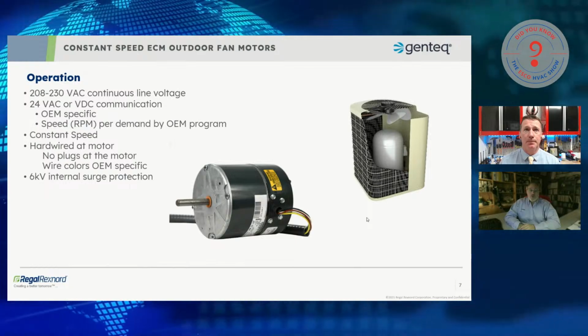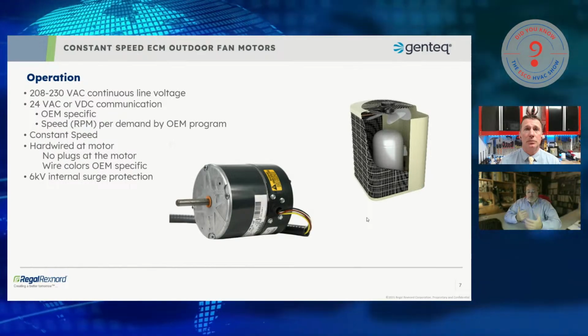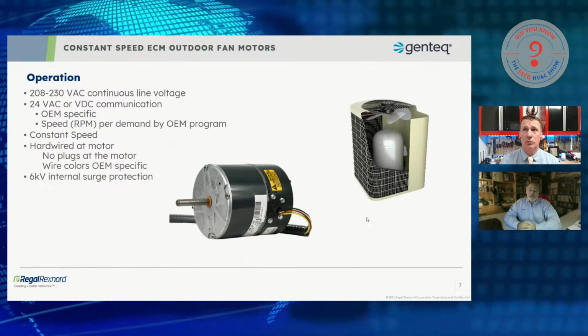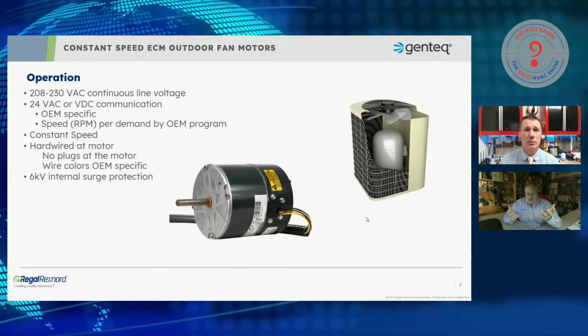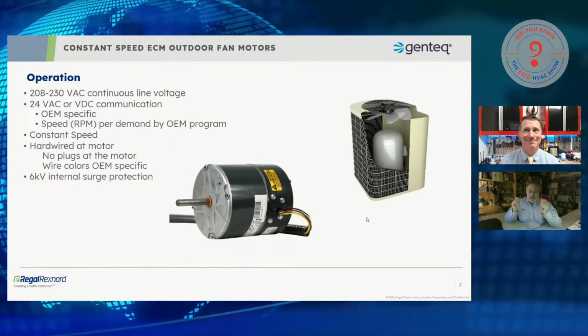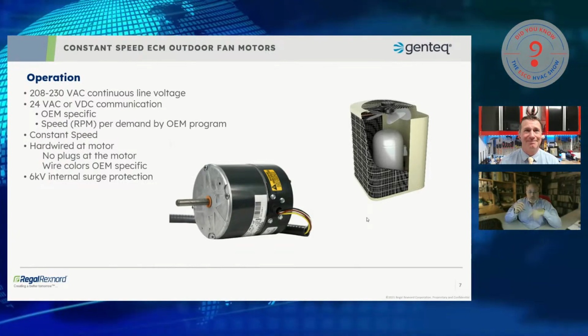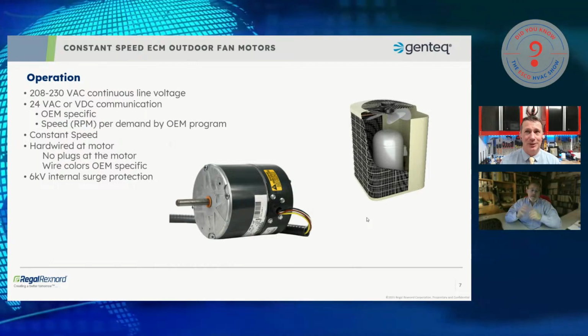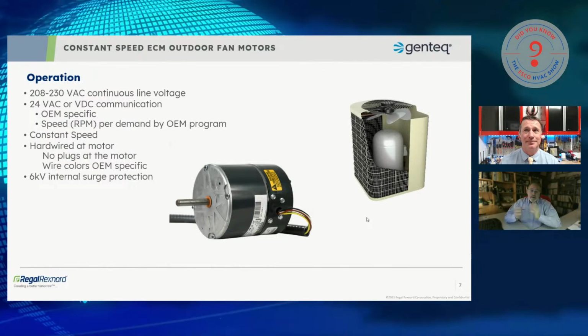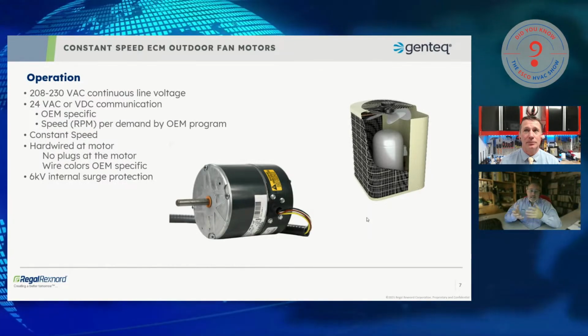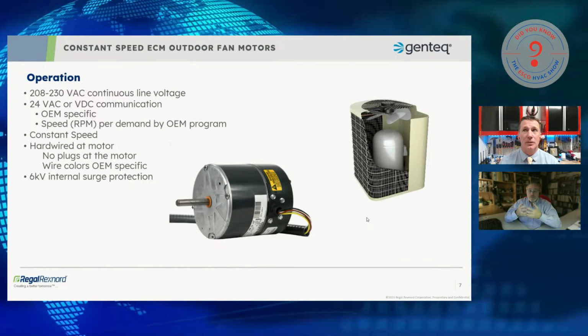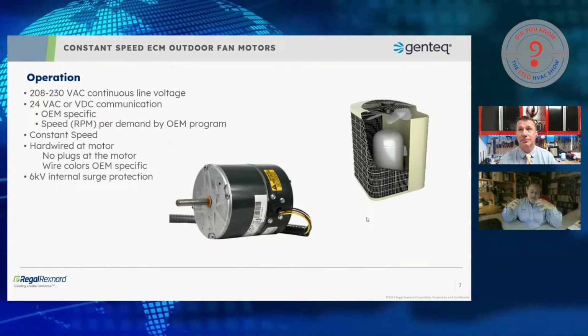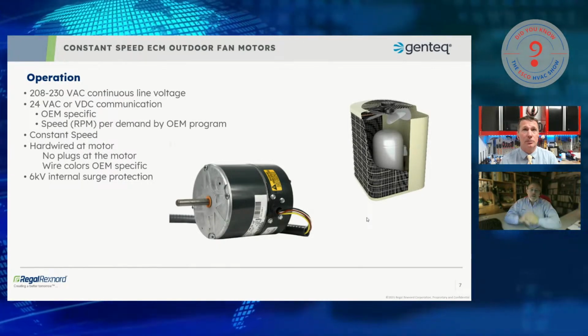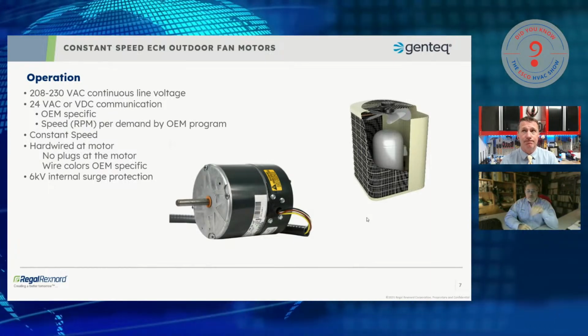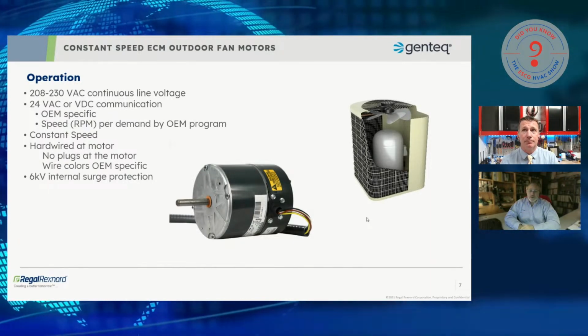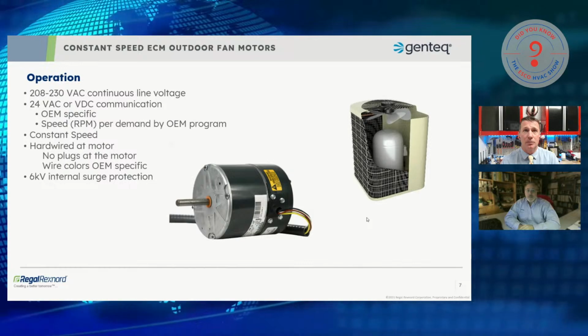So in the early days of drives, you may remember or have taught even Hall effect sensors, where you've got a couple of pickups, and those pickups read how many times the motor goes past the pickups, and it feeds back RPM. Well, our rotor being permanently magnetized is basically its own pickup, its own magnetic source, and then the windings of the stator are the pickups themselves, so they can read that back EMF as it goes around in the motor, and it knows its own operating RPM.